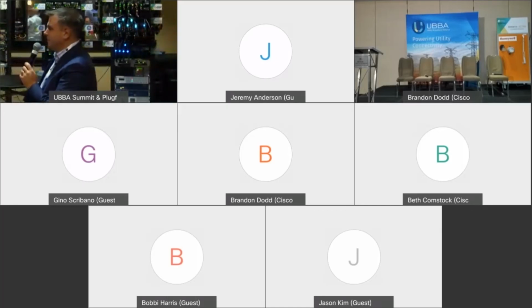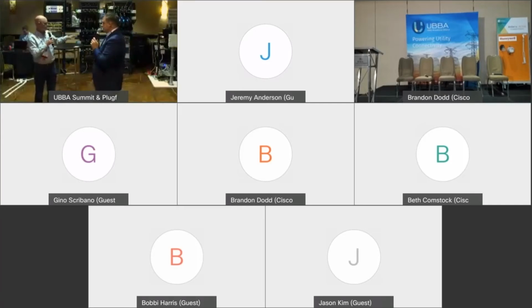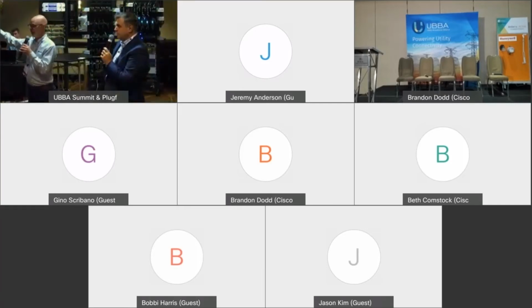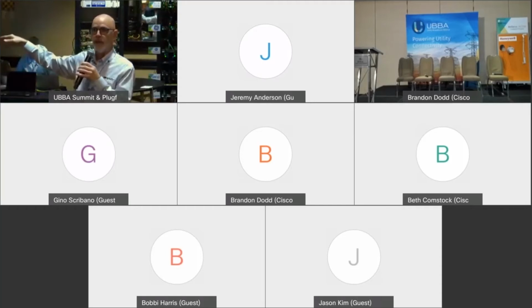All right, so what we're doing is right now these devices are running on Ericsson 900. Ericsson is taking their 900 down, and that was quick. And now we show that we are able to communicate over Ericsson 900 through those devices. And so what we do is we shift what we're trying to poll with DNP, and we start polling a different IP address that should be the public IP.